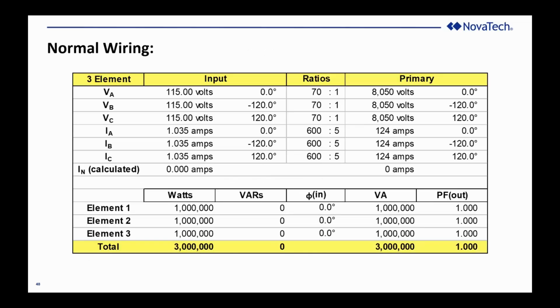So here is the screen right out of the 3-phase power calculator that we set up. I type in the amount of voltage. I type in the phase angle. I type in the ratio so that I can see the values in primary and secondary values at the top. The lower half, the watts and the VARs, is only in primary units.